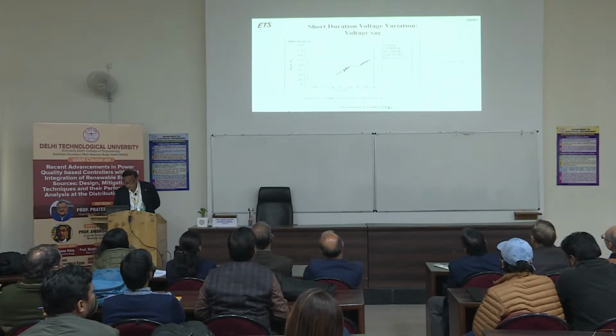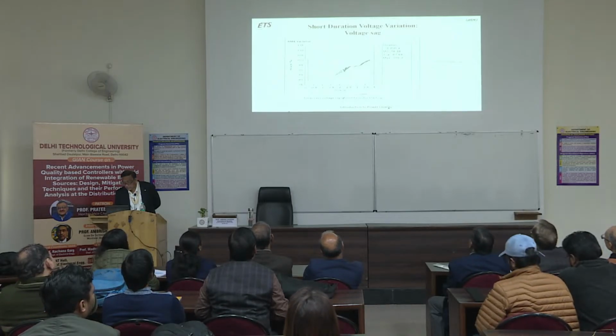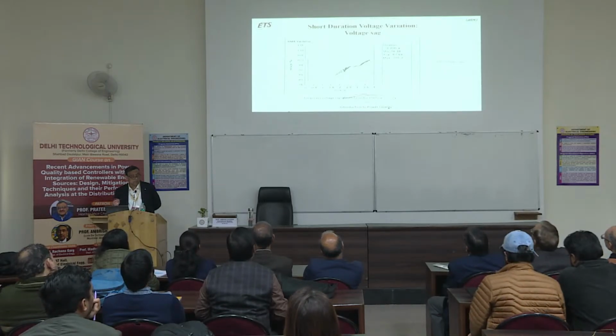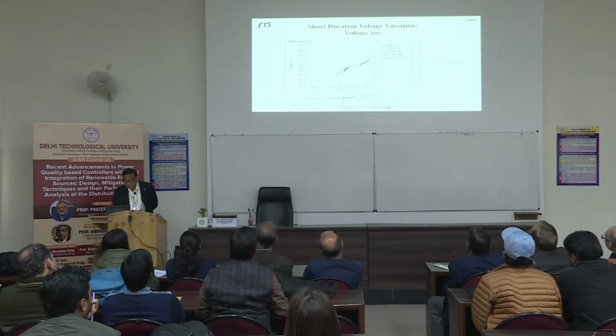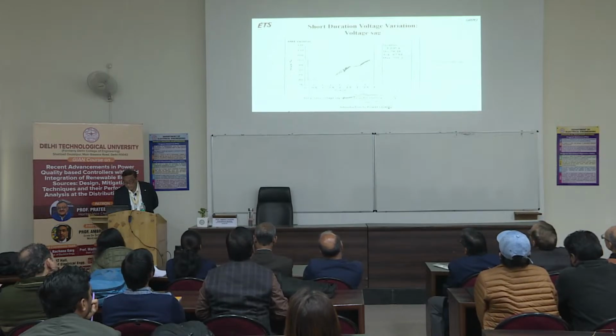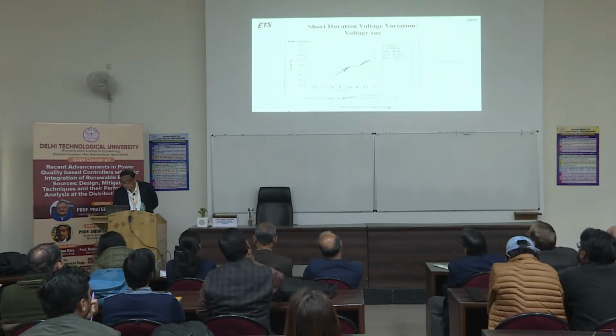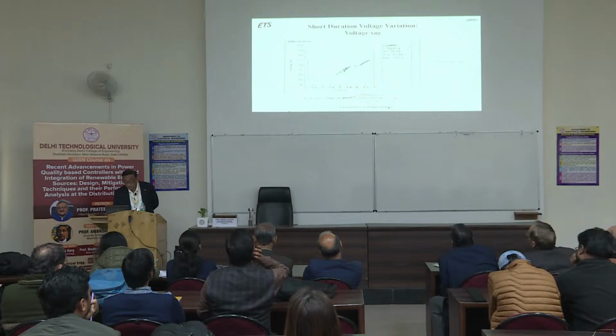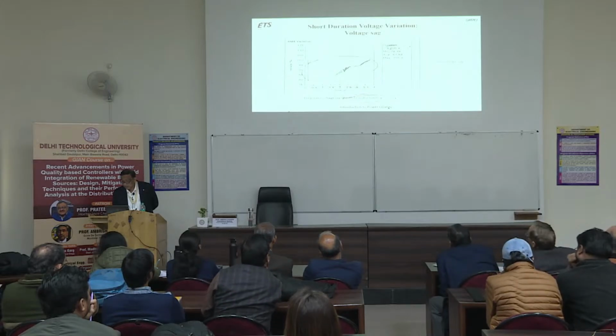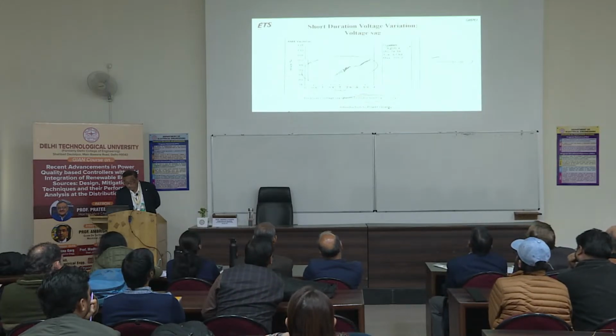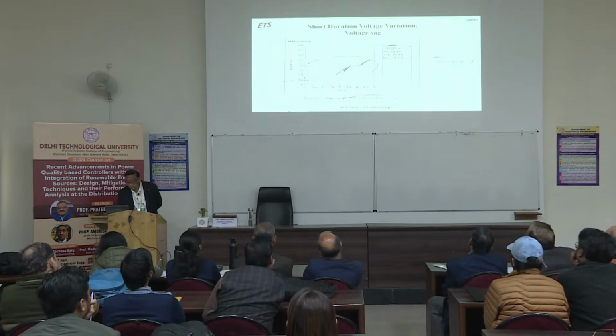And this is the voltage sag caused by motor starting. As I was telling you, if you have a large induction motor, then for a few seconds, like in this case 3.2 seconds, you have a voltage sag here. And 20% voltage sag because the voltage has gone down to 80% here.